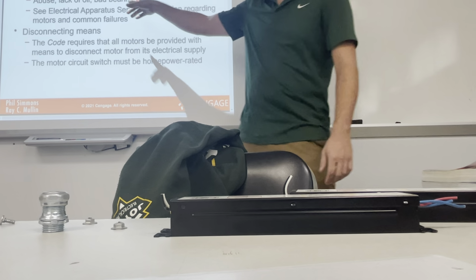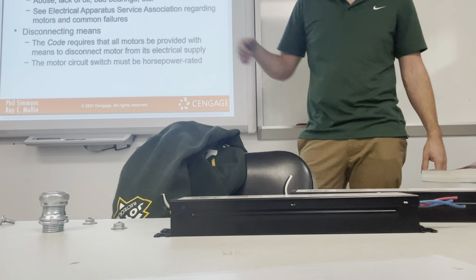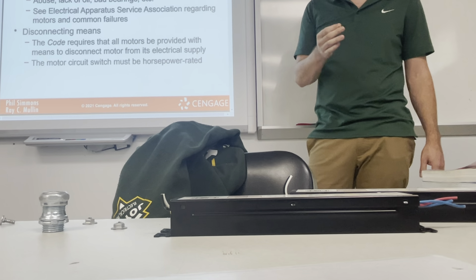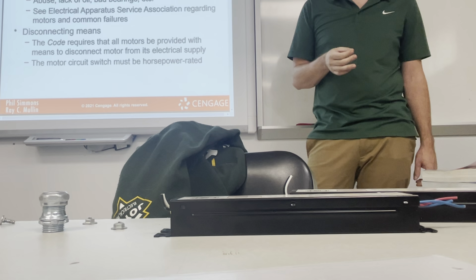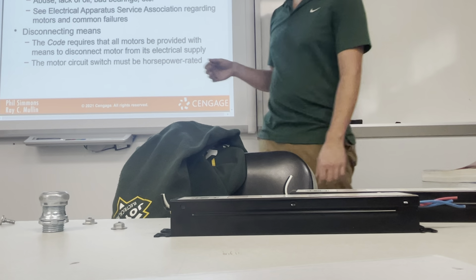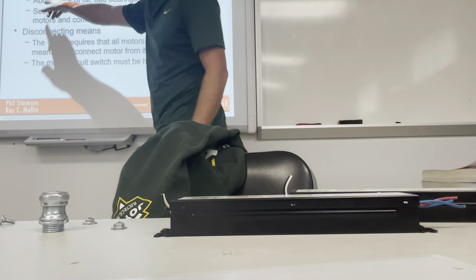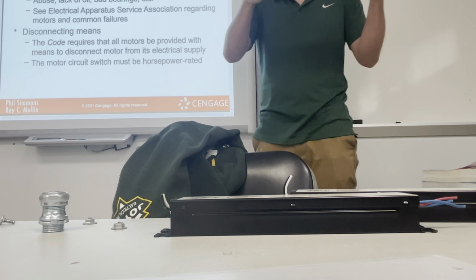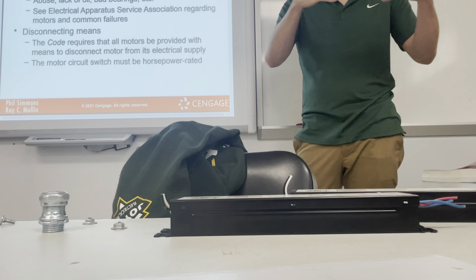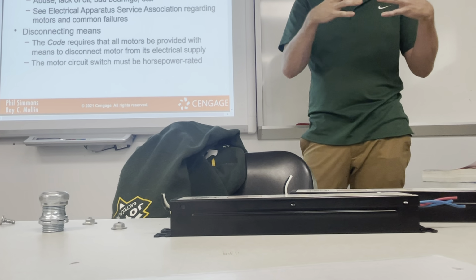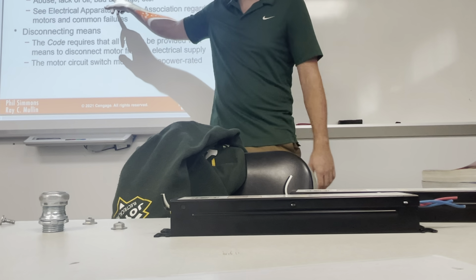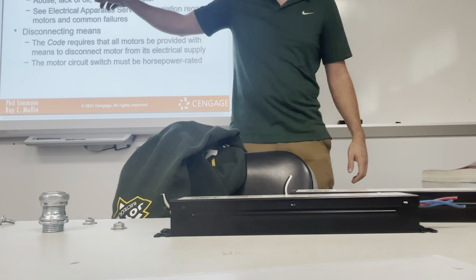Because the alignment tolerance for a lot of big motors is only like 1 or 2 or 3 thousandths of an inch. So if something gets bumped, jostled or abused, that shaft alignment is going to come right off. And then what's it going to destroy? It's not going to destroy your motor right off the top of the head. It's going to destroy the bearing in it, which will then destroy the motor.